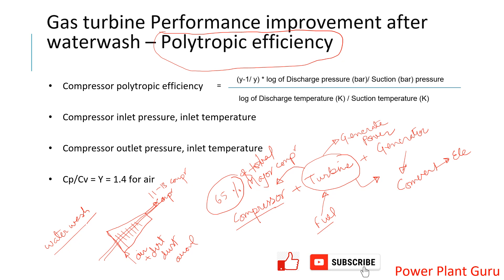To take care of blade fouling, a water wash activity is carried out using a detergent-based process. I will make a separate detailed video on water wash. The key idea here is to show the concept of efficiency calculation before and after water wash. By washing the compressor blades, you can compare polytropic efficiency before and after water wash to understand how effective the water wash activity was.